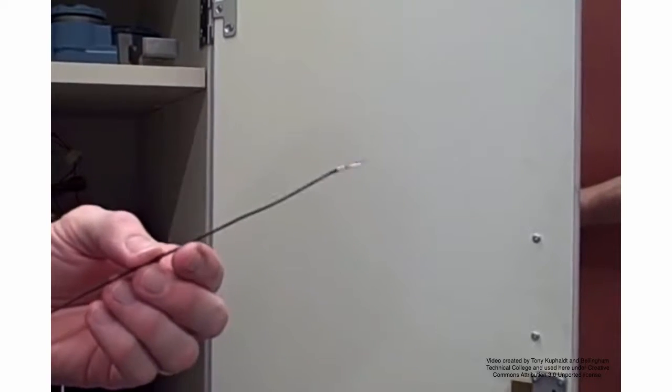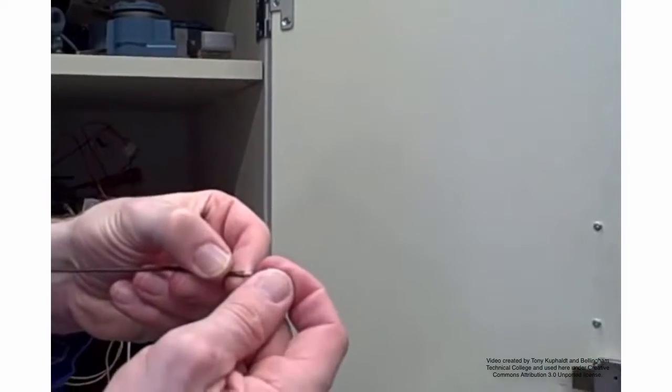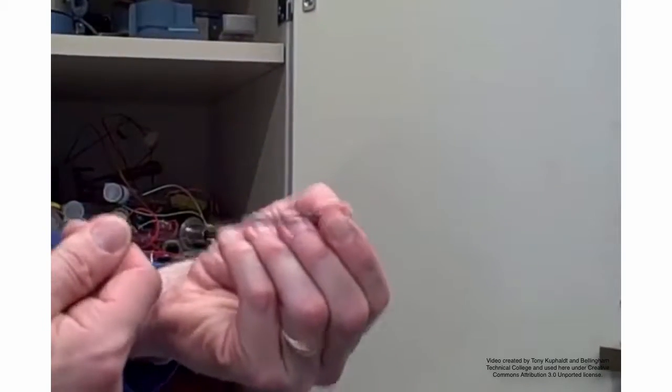This right here is thermocouple grade wire. You can tell that from the brown sheath. And if we simply took these two wires here and twisted them together, or spot welded them, or otherwise clamped them, or silver soldered, that itself would form a thermocouple junction.